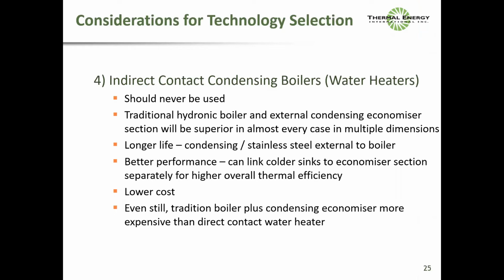And then I guess another one, since I have you: according to your experience, what's the recommended heat exchanger material when you are recovering heat from flue gases from bunker fueled boilers, diesel fueled boilers? I think that's similar to when I brought up the oil boiler, right? Yeah, bunker and diesel. Diesel is one step, bunker's another. Diesel, no problem with direct contact using stainless steel. Bunker, it depends on sulfur. I have to qualify, there's low sulfur diesel, but I'm basically using traditional levels. In bunker, the sulfur levels are so high that your 304 and 316 is no good. When we're doing diesel, I think we usually do 316.